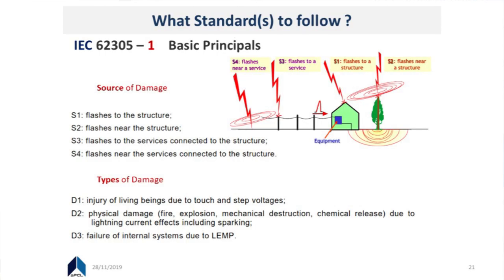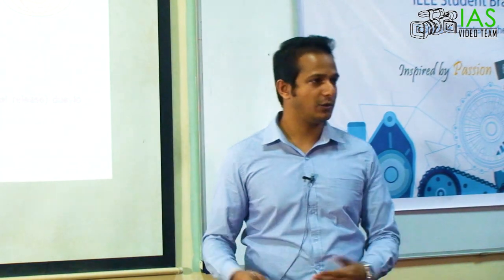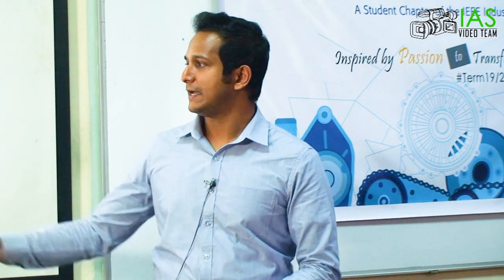And what types of damages? D1, D2, D3. There are three damages: injury to living beings, physical damages to our structures, and failures of internal systems. First is injury to living beings, maybe human or livestock, or the physical damages which cause a huge recovery cost, and failure of internal systems, much more critical these days. The continuous running of servers is more crucial nowadays.